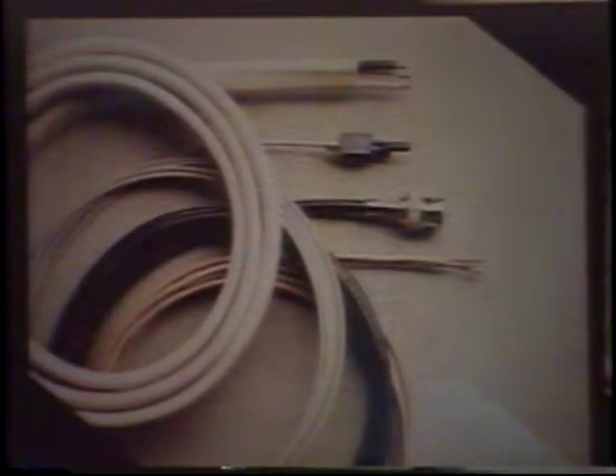All of them are designed to lower installation costs by using less wire, wire already in place, or no wire at all. If wires are needed, the LonTalk twisted pair transceiver lets up to 64 nodes connect to a common twisted pair cable, even draw their power through that cable, and do it for distances of a mile or more. There are actually two twisted pair transceivers. The first transceiver supports a data rate of 78,000 bits per second. The second transceiver supports 1.25 million bits per second. Using a common cable saves wire, saves time, saves materials, all of which ultimately lowers cost.